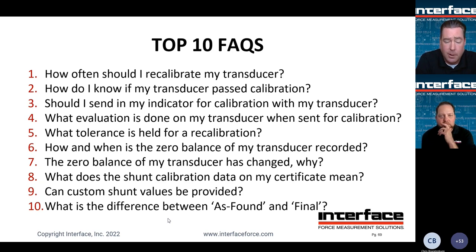The example I'll use is our gold standard systems that ship with a load cell, CX box, and an indicator. If you're calibrating the CX box at your lab, you can use it to calibrate your 9840, and you still have a traceable measurement, meaning you can send back the load cells, have them calibrated in millivolts per volt. No need to send in the indicator. If you have a dedicated load cell you're using with the 9840, and you want your cert to read as applied forces versus indicated reading, yes, it needs to come back in for calibration.